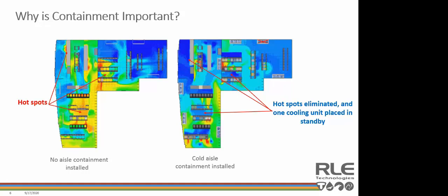The CFD image on the right, however, shows improvements after installing just cold aisle containment, including elimination of hot spots, which allowed an increase in cooling unit set points of 5 out of 6 cooling units, while still allowing an entire cooling unit to be placed in standby mode, thereby increasing cooling redundancy, efficiency, and overall capacity.